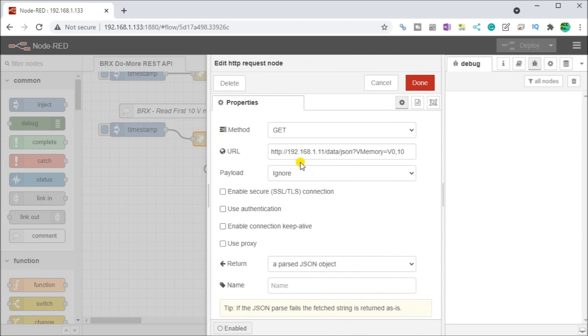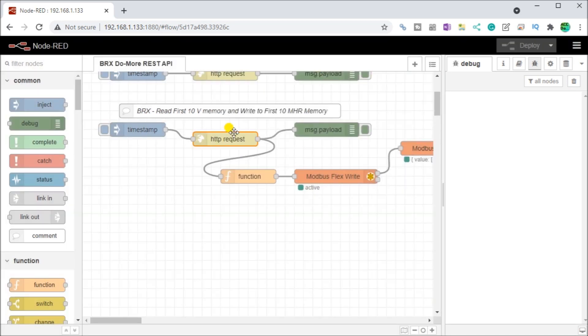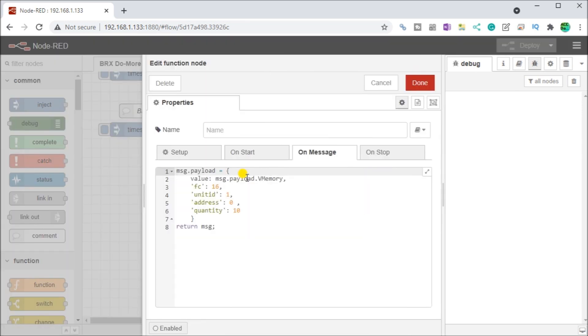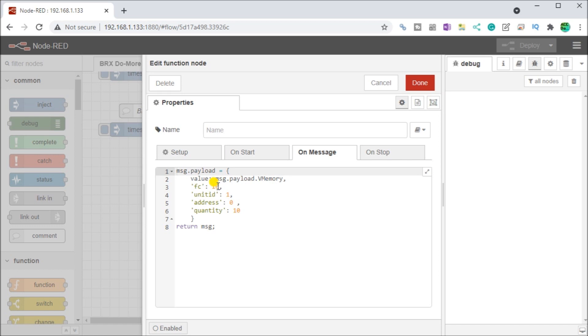Here, what we're doing is we're going to read the first 10 V memory areas. Then we're going to bring those back in again as a parsed JSON object. Once we do that, we're going into a function block here, which will then take that V memory area. You can see that we just use it as straightly as a JSON value here in our payload. We're going to be using multiple write using Modbus.